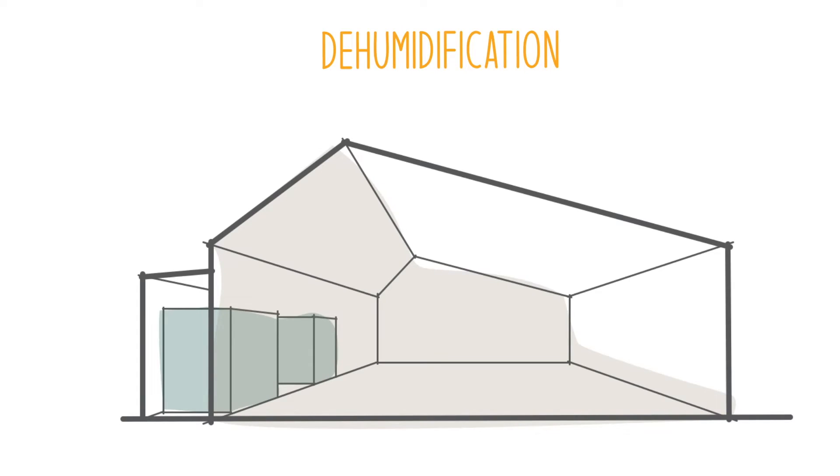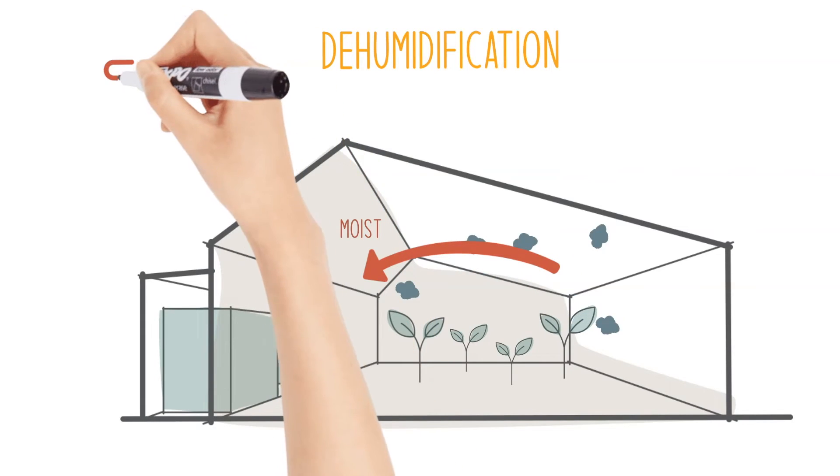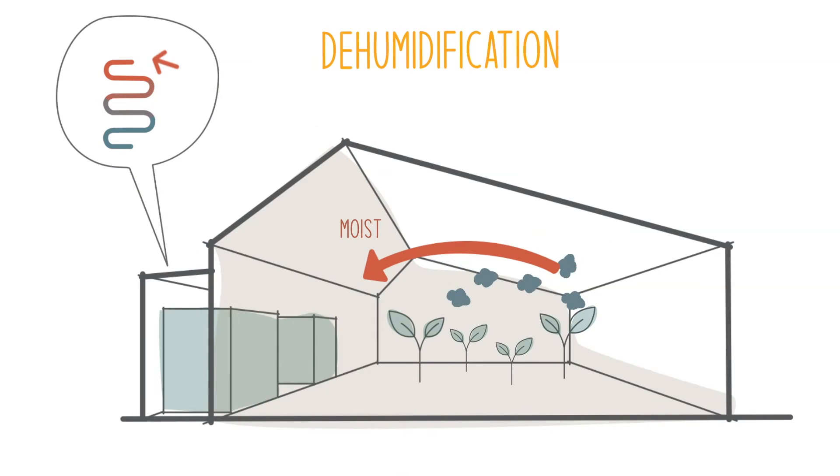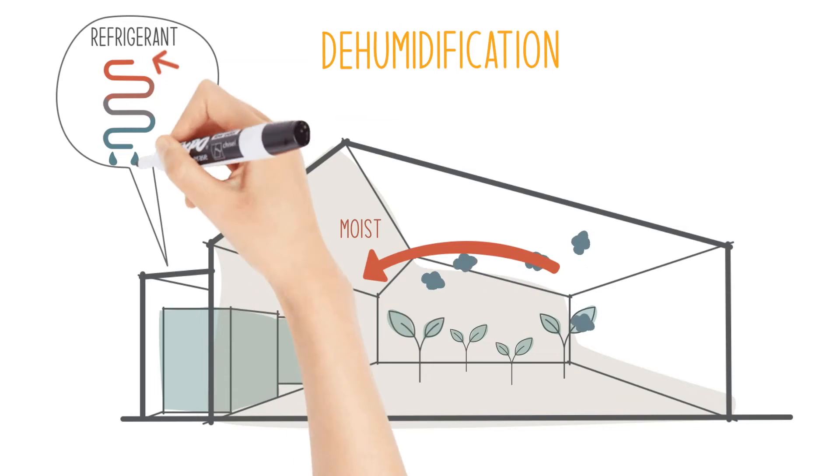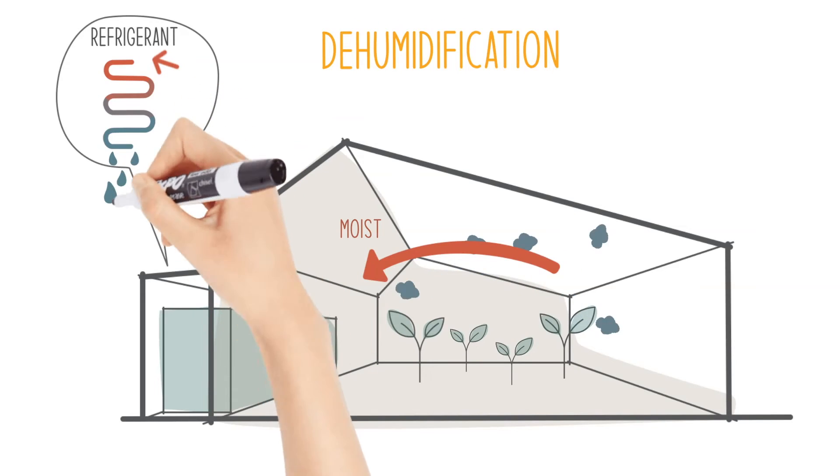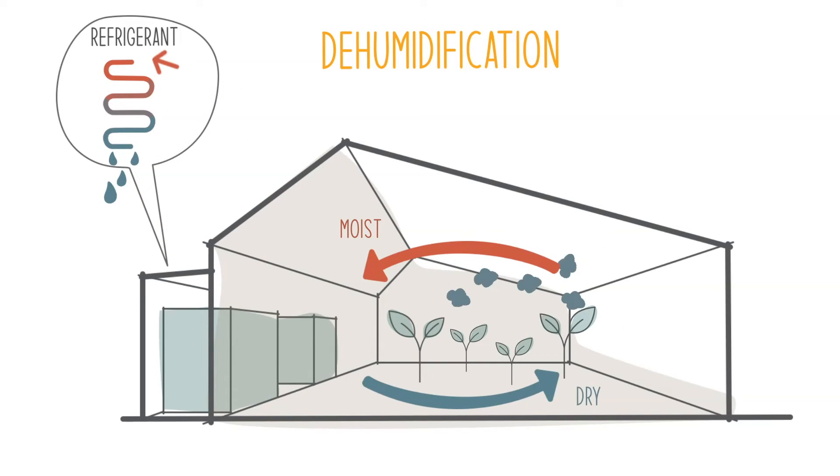The same process can be applied to dehumidification. In a grow environment, the excessive moisture introduced by plant transpiration is contained as water vapor in the air. The same air is then sucked towards the HVACD system. When air makes contact with the refrigerant cooling coil and reaches its dew point, condensation occurs, meaning dehumidification is happening.